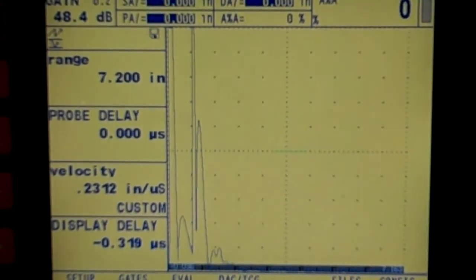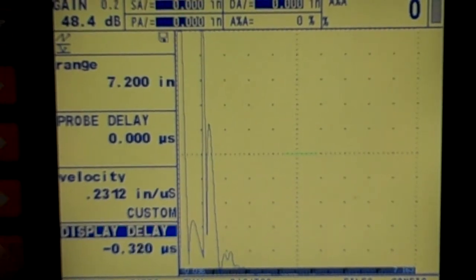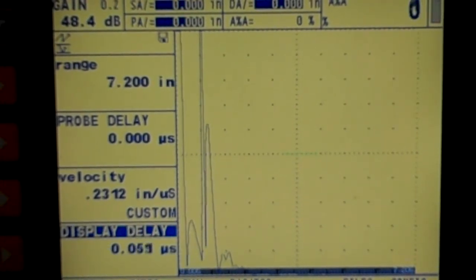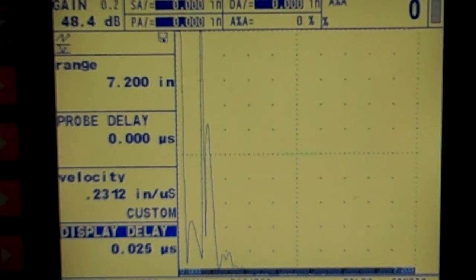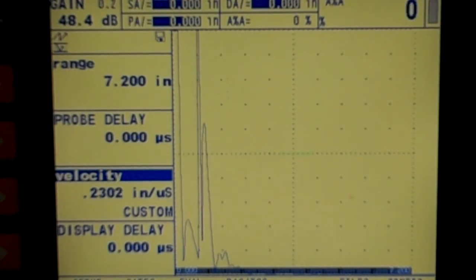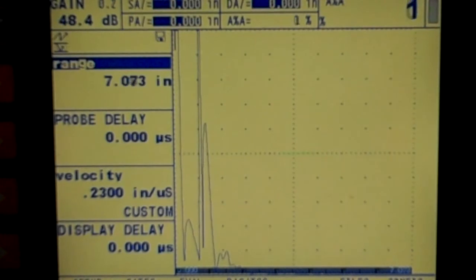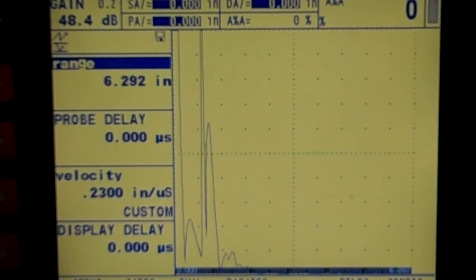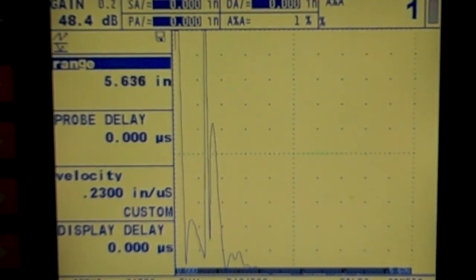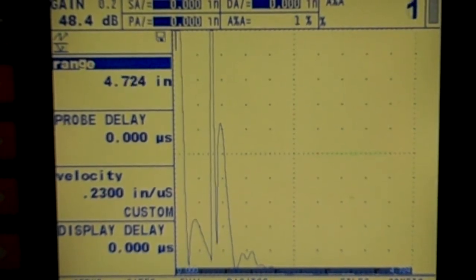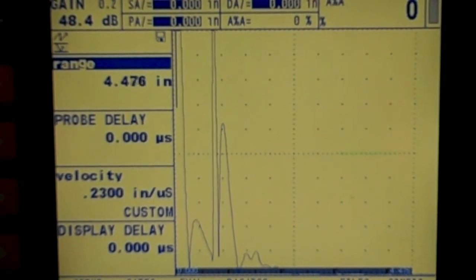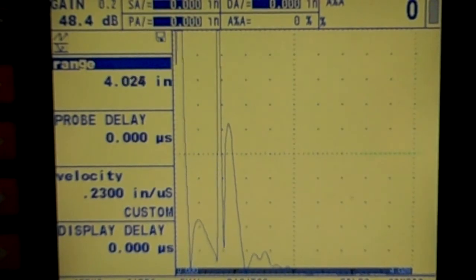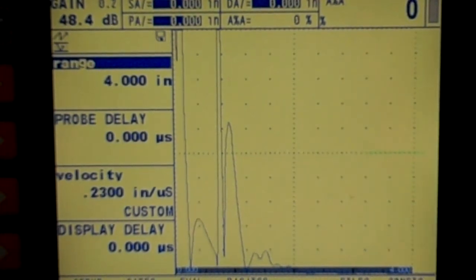We have a 7 inch range, a roughly 7 inch range, 0 probe delay, and then a little bit of display delay. I'm going to take that all back to zero. We're messing with steel, mild steel, so I'm going to take this back to 230,000 inches per second. I'm just going to go to a 4 inch range just for fun so I can get started and see where I'm at here. There's a 4 inch range. Zero, 100%, that represents 4 inches.